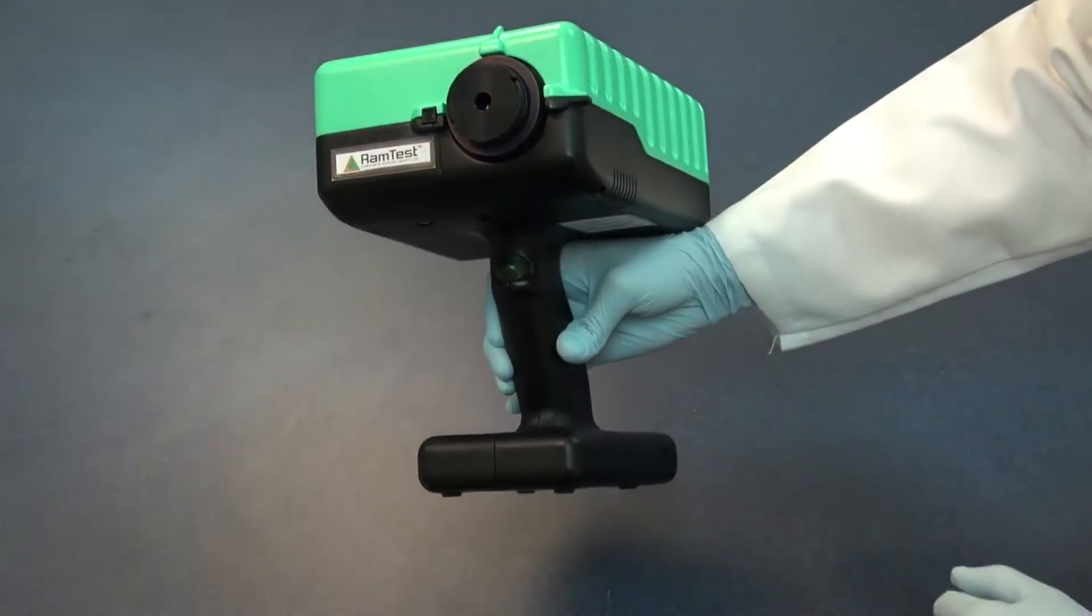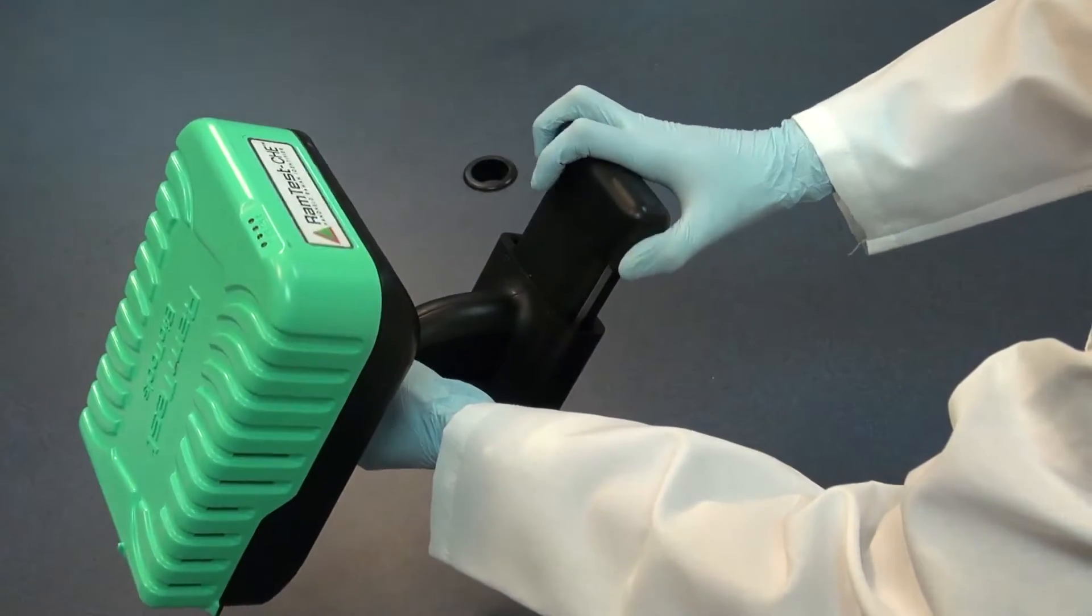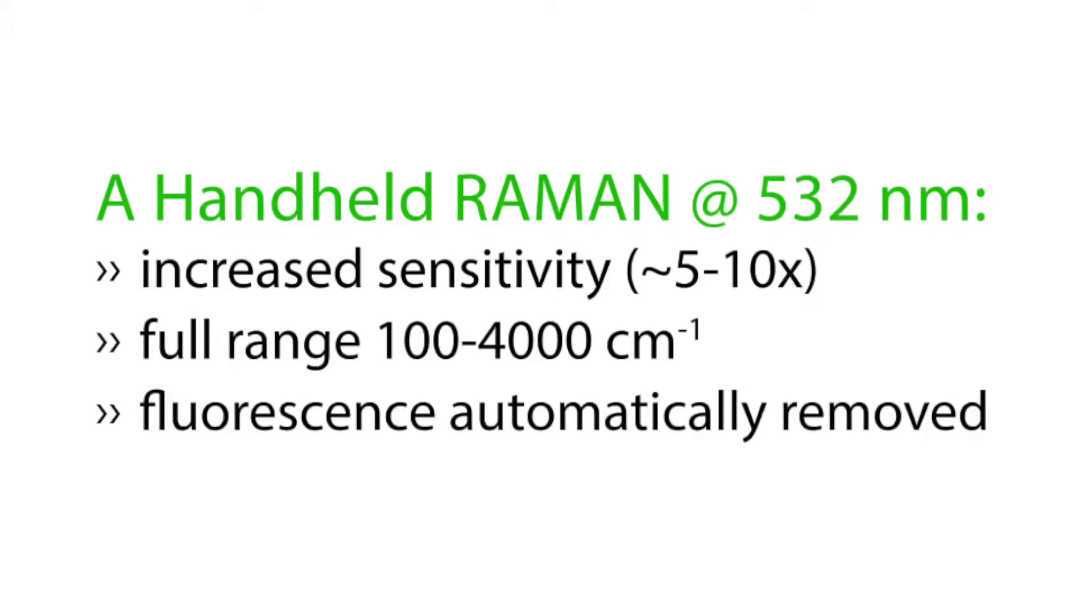With an operation start time of under two minutes, RamTest uses a Bluetooth connection and is powered by a built-in battery pack or AC adapter. RamTest uses a 532 nanometer laser.